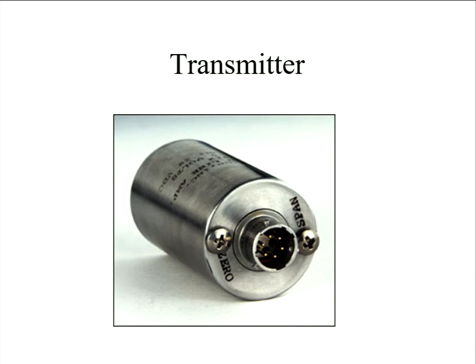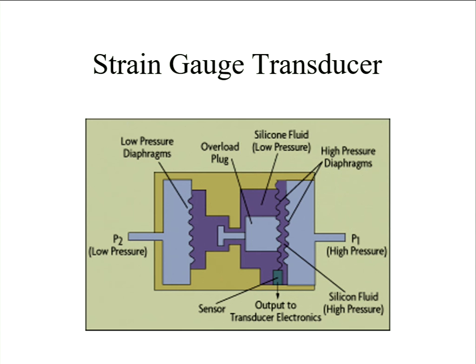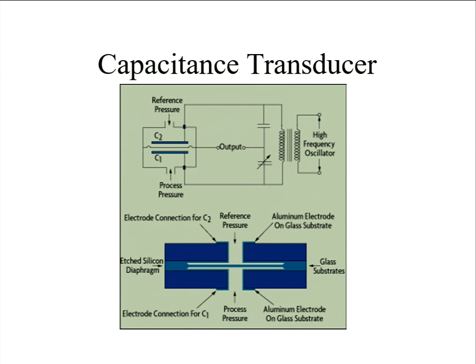If you want digital, you've got your analog, and then you've got to do analog to digital conversion, and you've got to be careful that you're getting the resolution that you need out of it. So you need to understand what that is, using 8-bit, 12-bit, 16-bit. You can get parallel or serial inputs. Field bus compatible devices are now popular, particularly, I guess, on the larger process plant. Again, resolution, and your A to D converter does play a part in resolution. It depends how important resolution is to you.